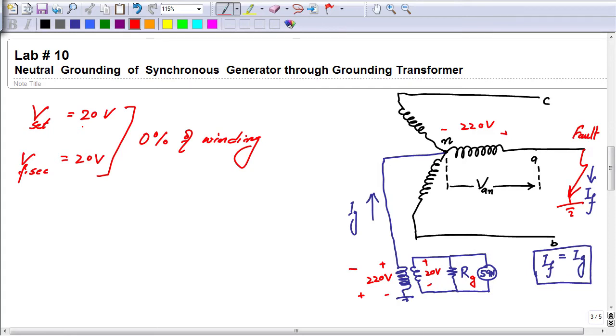So let's make the adjustment, and in the second case, make Vset equal to 10 volt. Let's see its impact. Now in case of a fault at the terminal of this winding of the generator, we get 220 volt across the primary of this grounding transformer, 20 on the secondary, and Vf on the secondary would be equal to 20 volt. The relay would respond to this fault and open the circuit breaker. Yes, the fault has been detected.